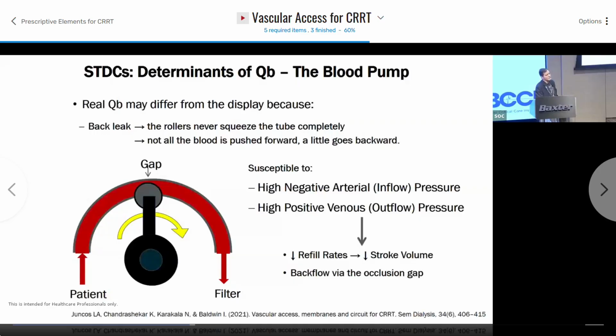So people ask me, well, how is blood flow different? Well, you basically have a peristaltic pump that's pushing blood forward, but not all of it goes forward. Some can go backwards if I have a high negative pressure or I have a high positive pressure on the post-pump area. And those aren't absolute values. It's a ratio between the two. That's why I can't give you one number and say, oh, this is a problem. No, it's that ratio. And that's why it's different for different settings.